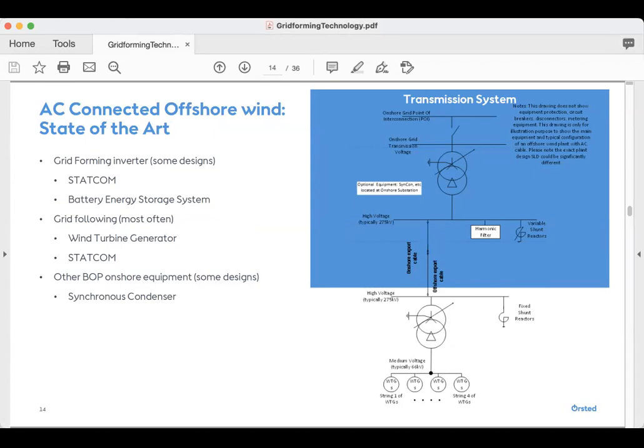In some of our designs, most often we try to use grid following inverters for STATCOM. But as I said, there have been exceptions when we have actually used grid forming inverters for the STATCOM. As for the other balance of plant onshore equipment, if we see a very weak grid at the point of interconnection, we've had synchronous condensers to improve the grid short circuit level and the grid strength onshore. So that's typically what's done today.